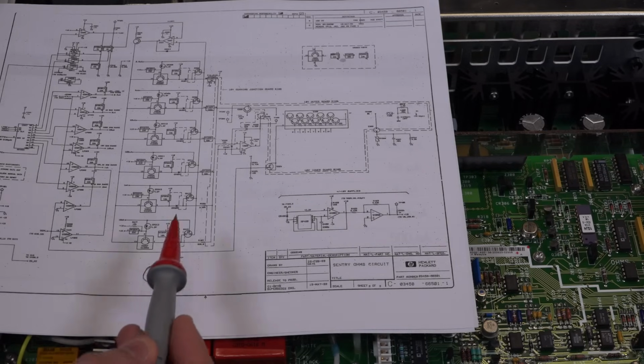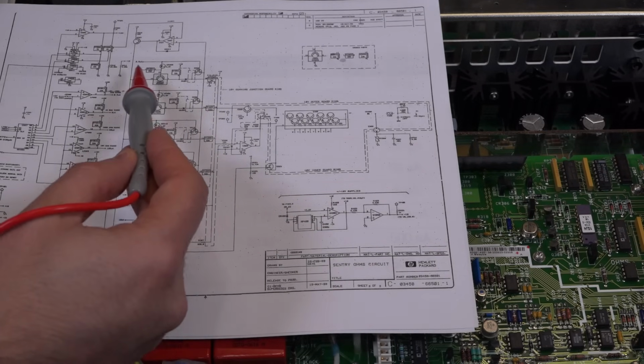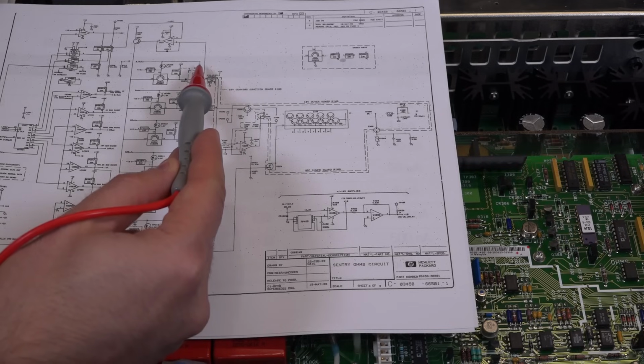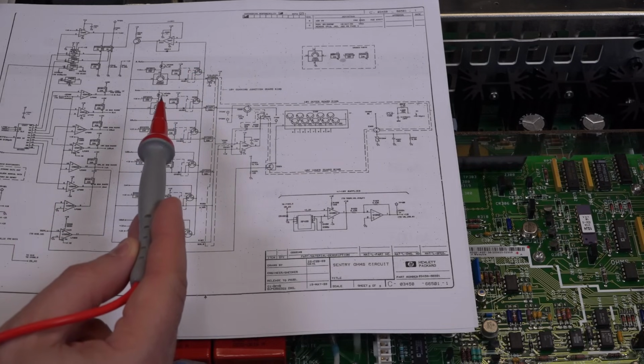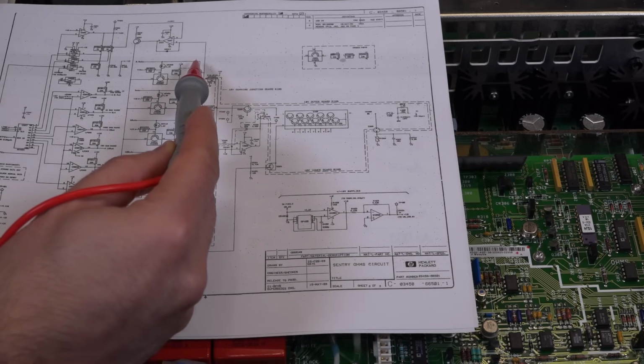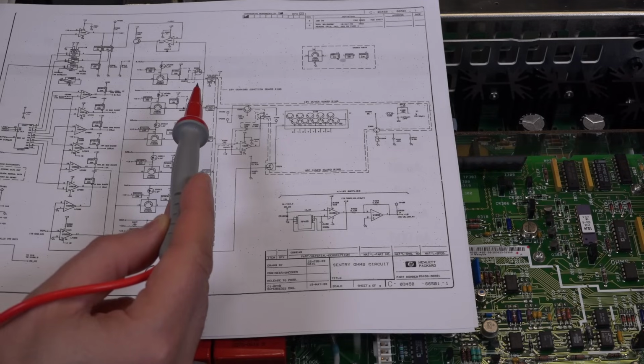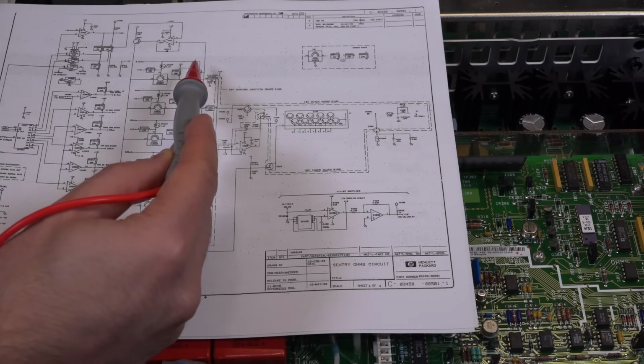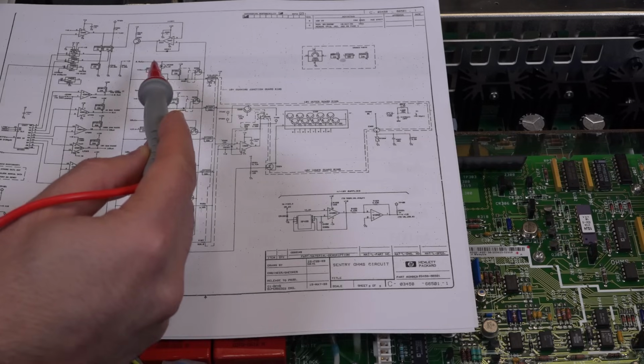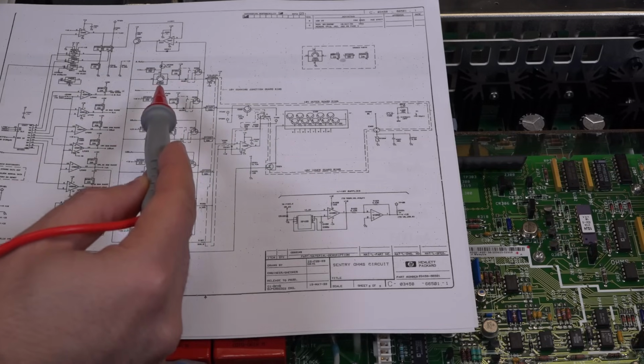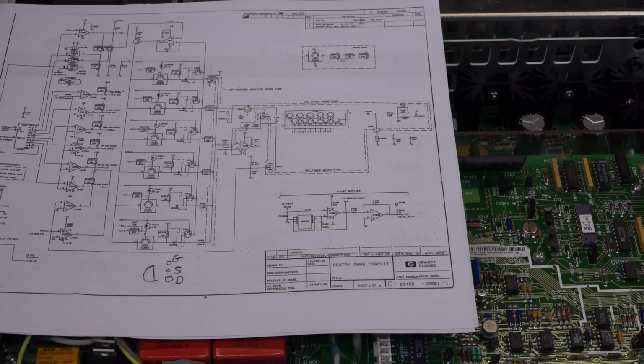So I'm going to start from the lowest one, which is this 500 nanoamp one. If I measure the gate over here and I set the range to the highest range, the gigaohm range, I should see a signal here because this path should be enabled. But as I increase it, eventually that signal should disappear once I'm 3 ranges up, because this is no longer relevant, it has to jump to the next one. So that's a quick and easy thing we can try.